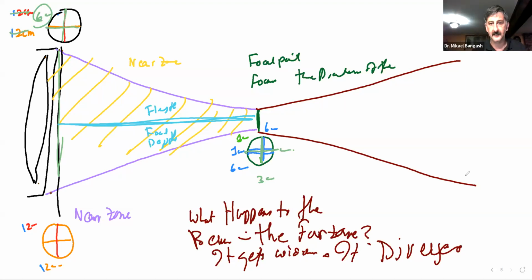Now, just in this instance, because practically it is going to be a little bit different, if this distance here, the focal depth or focal length, we can check any distance, it doesn't really matter, we can say it's focused at a depth of, let's say, 4 centimeters, which means our near zone was also 4 centimeters.